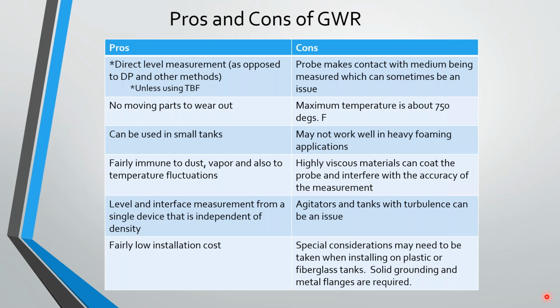What are the cons? Well, the probe does have to make contact with the medium that's being measured. That may be an issue in some cases, in which case we may need to look at non-contact radar, which I'll be covering next. Maximum temperature is about 750 degrees Fahrenheit, although now there are some new high pressure, high temperature devices coming onto the market that may actually exceed those temperatures.